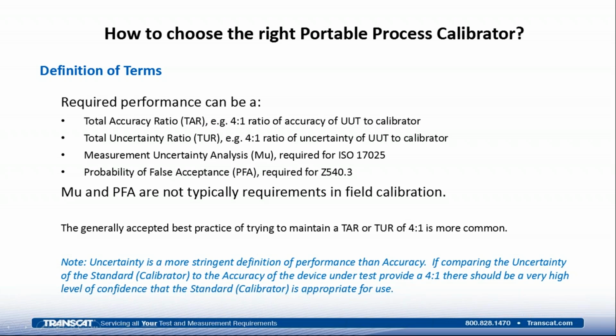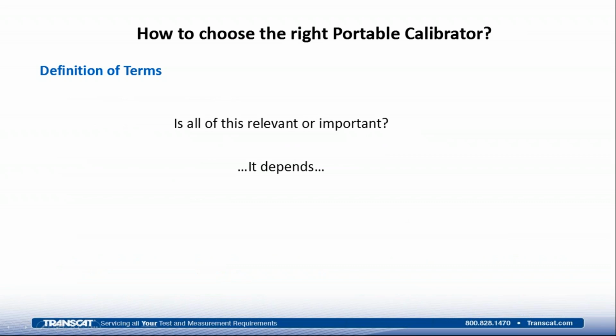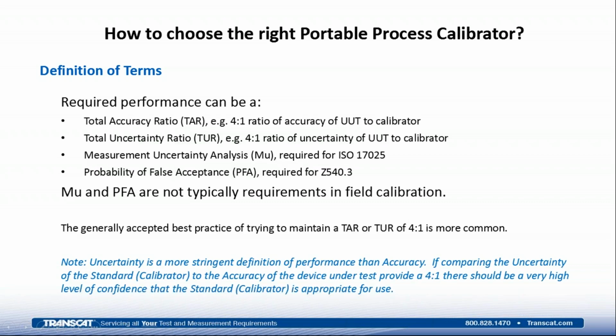So let me reset myself. Is all of this relevant or important? Well, it depends. Required performance can be defined a number of different ways. The total accuracy ratio would be the ratio of the device under test to the calibrator. So if the calibrator or standard being used is 4 times more accurate than the measurement device, then we're maintaining a 4-to-1 accuracy ratio. Similar, but different, because we're talking about uncertainty, would be the total uncertainty ratio. And again, if the uncertainty of the calibrator was 4 times better than the uncertainty of the measurement device, if known, then that calibrator would be appropriate if we're using that criteria.